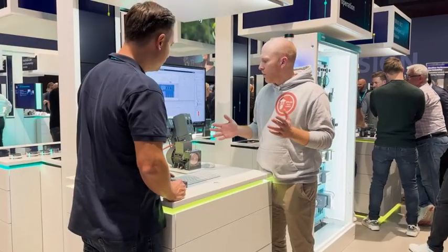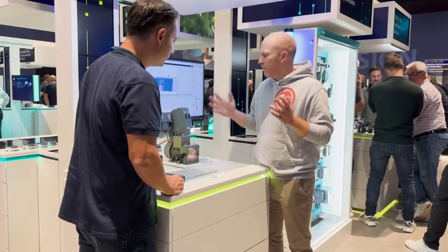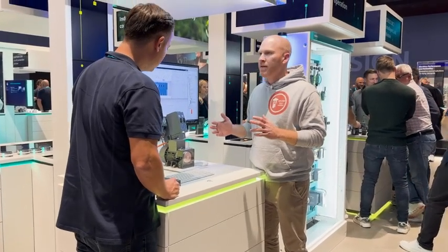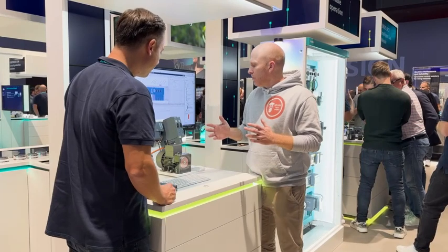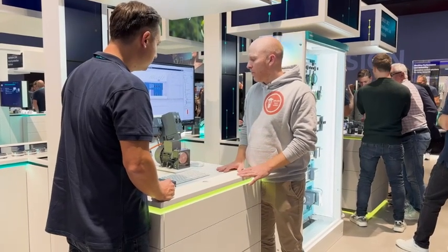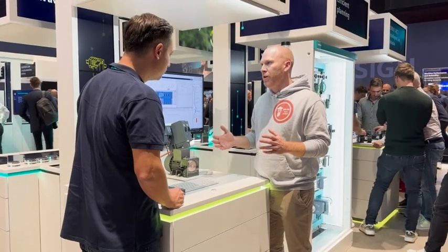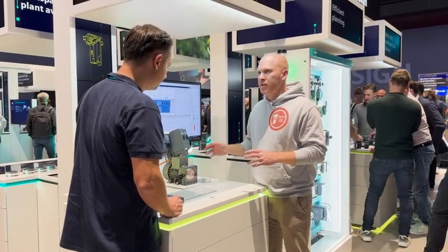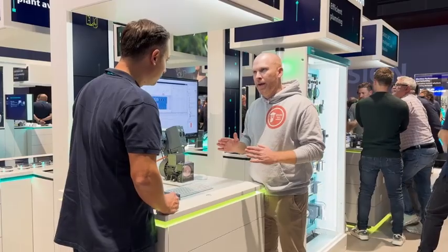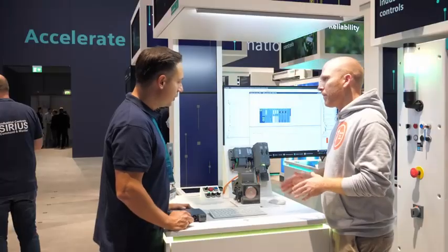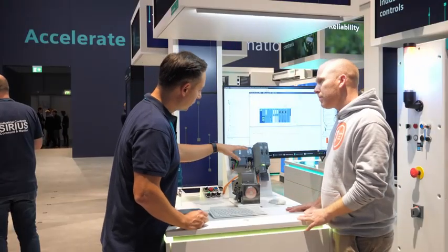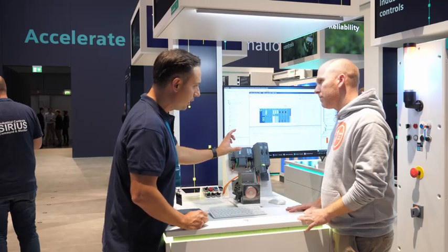So this is an optional accessory which facilitates the commissioning procedure. Yeah, now let's talk about another story in the lifetime of a machine, which is maintenance. As you told us, it's an electronic motor starter, but anyhow, when you want to change, for example, the motor, you need to make sure that the motor starter is disconnected from the motor in a mechanical way, not just electronic. Yes. So we have a galvanic isolation here because we're switching all three phases.